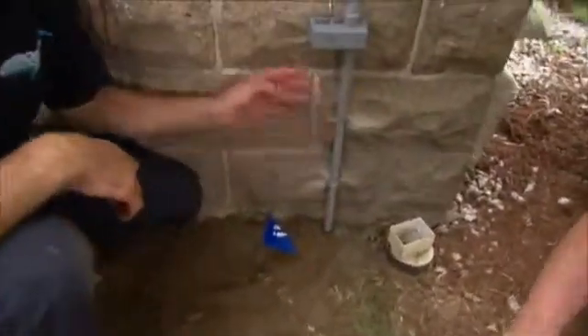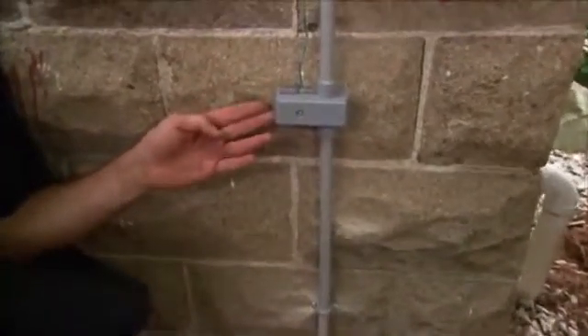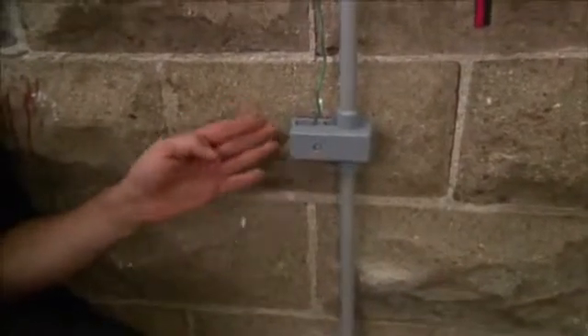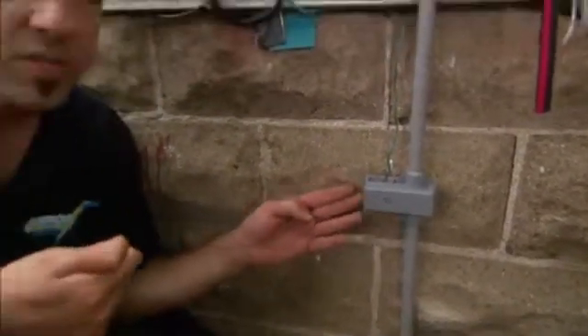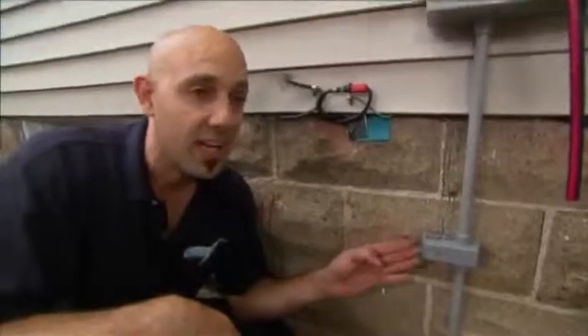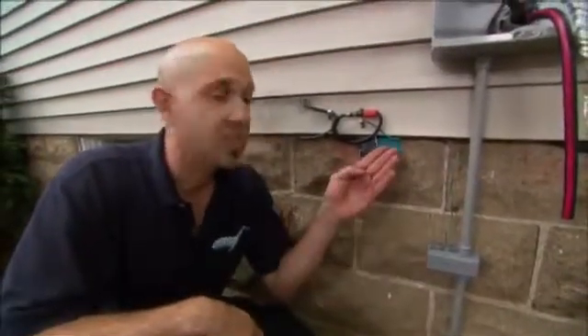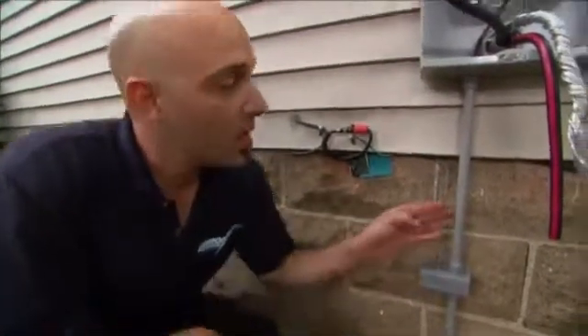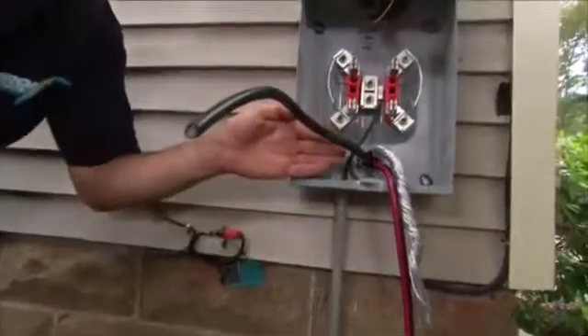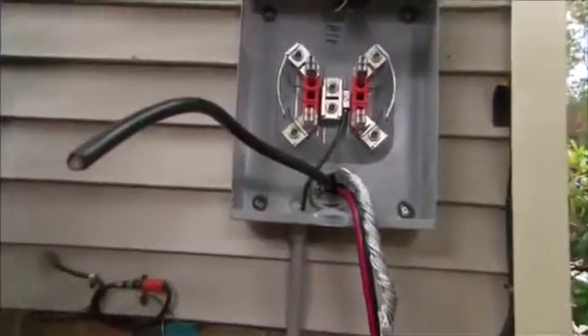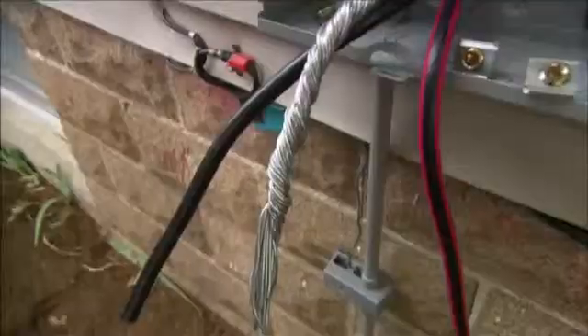So we've completed burying the wire underground, which connects this ground rod to this ground rod. The cable travels underground up this conduit to this inter-system bonding termination. This bonding termination allows the cable, internet, and phone companies to tie in safely to your system. You can see the cable's already been installed. The wire runs up into the meter socket. Now I'm ready to connect the power wires into the meter socket.